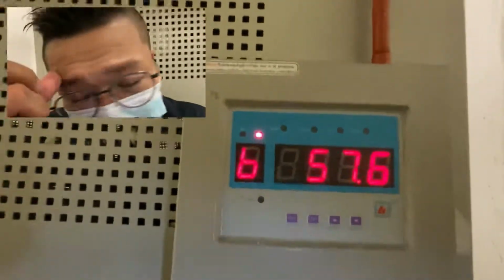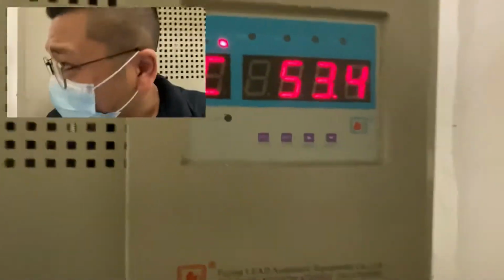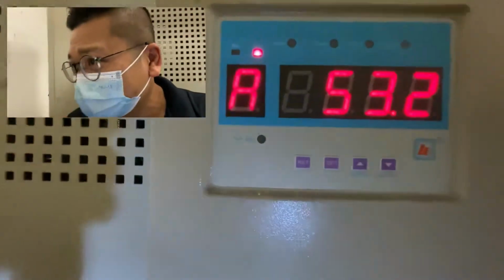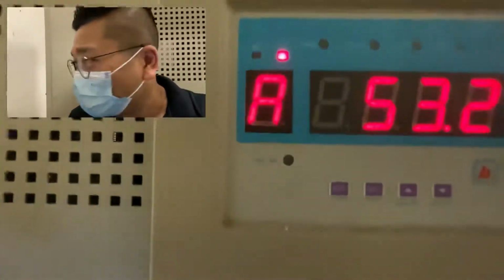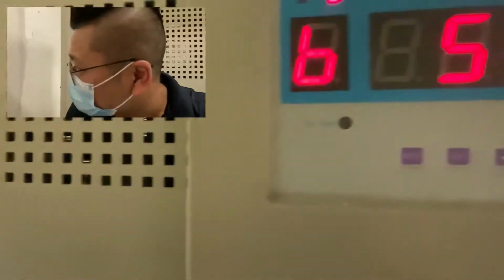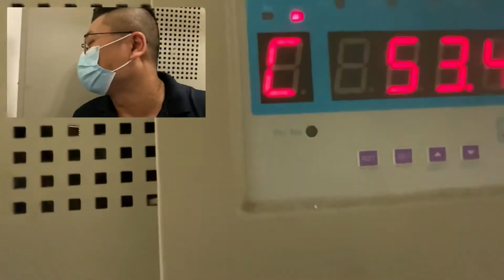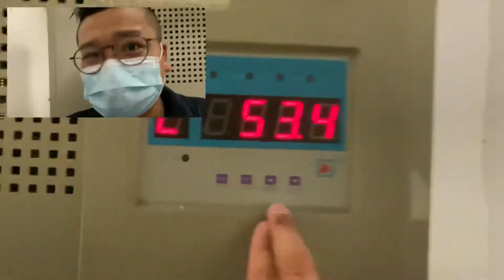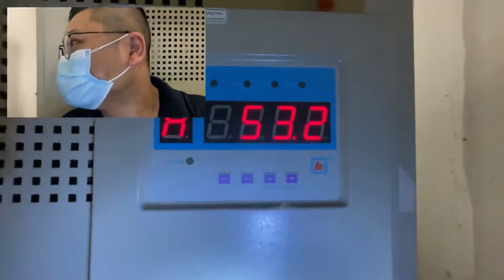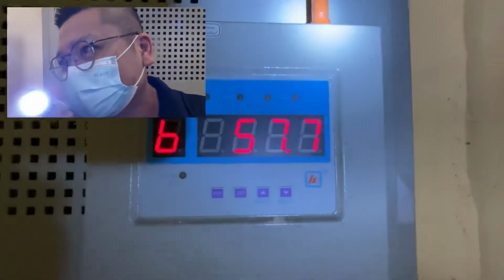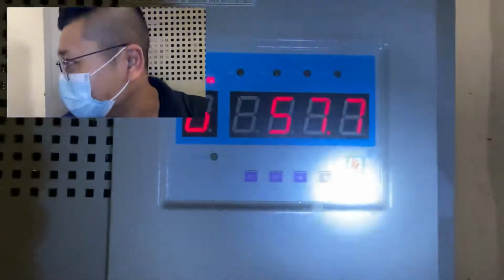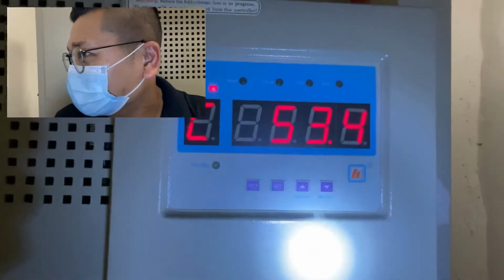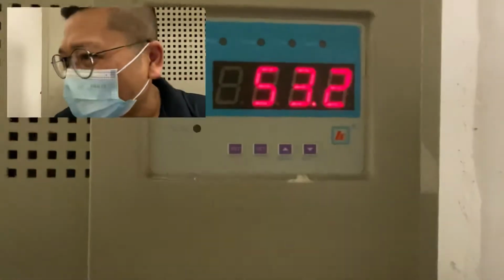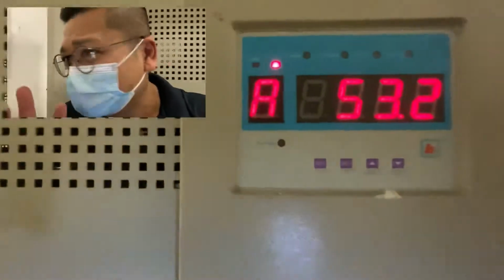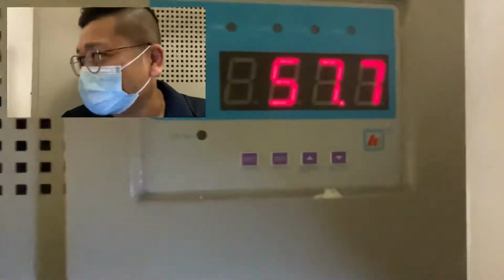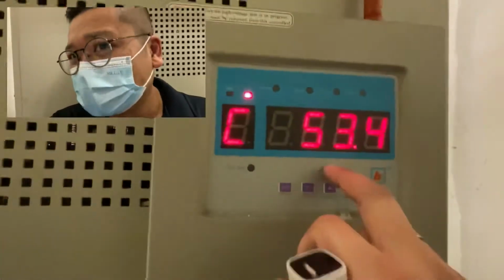So there's an air forced fan installed inside the transformer. Once it reaches a certain level of degrees Celsius, the air forced fan will operate. It will force the air inside and cool down the transformer. The setting is set from here. That setting is most probably 90. When it reaches above 90, the fan will operate, until the temperature cools down, drops below 80 degrees Celsius. But that range can be settable. Some use 70, some use 60. It's programmable from here.